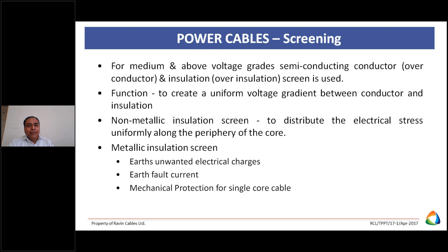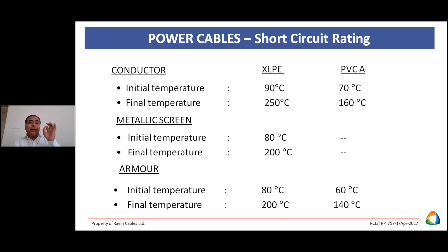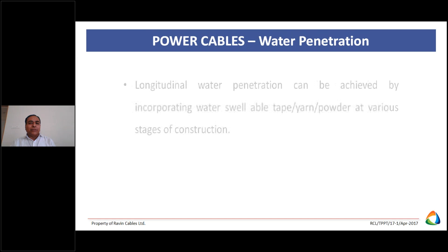Again, mechanical protection for single core cables. These are the basics. Now, with this, we are coming to the selection of the cables, how cables are selected based on your requirement. Before that, we require the short circuit ratings of your system. What considerations are required for PVC cables and for XLPE cables: what is the initial temperature, what will be the short circuit temperature, the final temperature, what will be your metallic screen temperature. These are basics while selecting or designing a cable. So these are the basic assumptions considered for the selection of the cable.